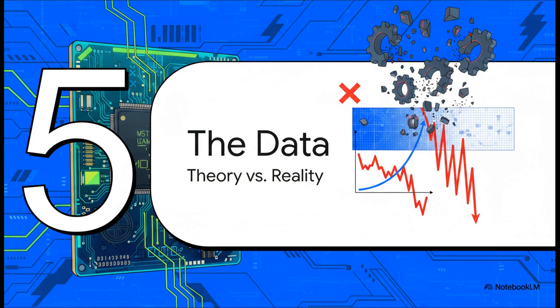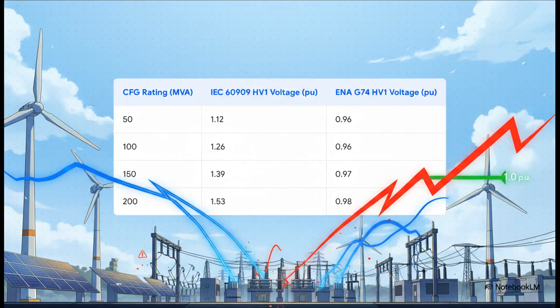This is where it all becomes crystal clear, and the problem is just undeniable. This table says it all. Just look at that IEC 60909 column. As you ramp up the amount of converter-fed generation on the system from 50 up to 200 MVA, the calculated retained voltage just keeps climbing to this ridiculous 1.53 per unit. Meanwhile, look at the ENA G74 column. It stays stable, right around 0.97, 0.98 per unit, exactly where you'd physically expect it to be.